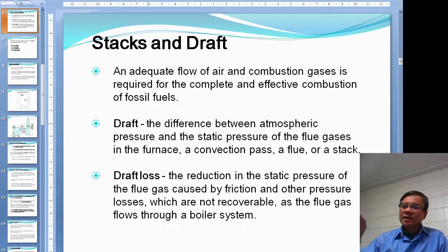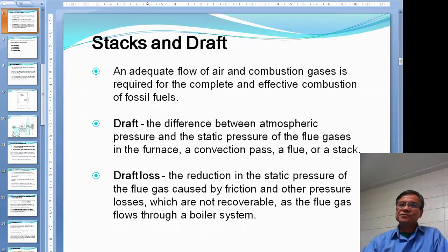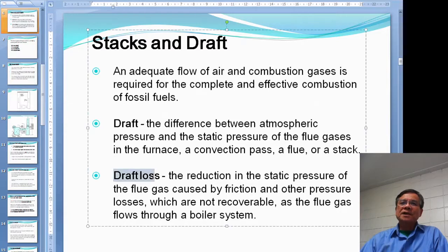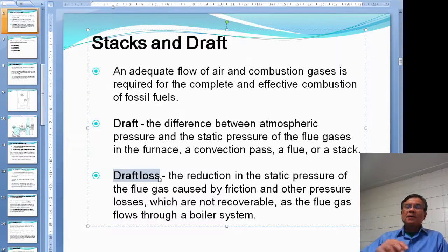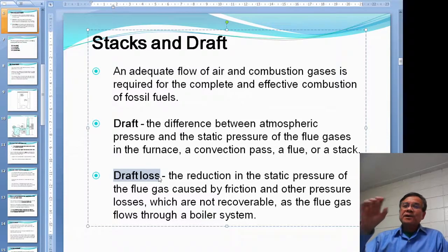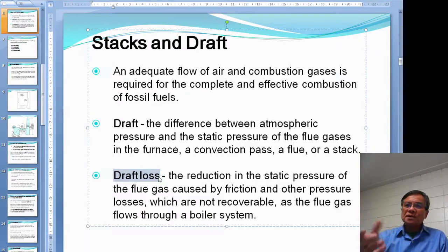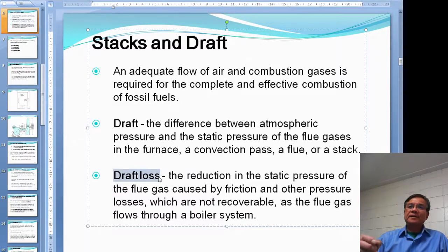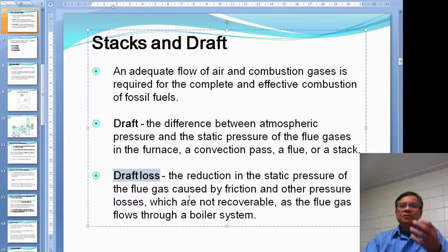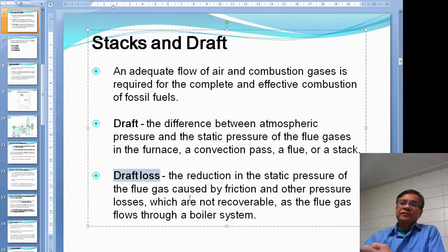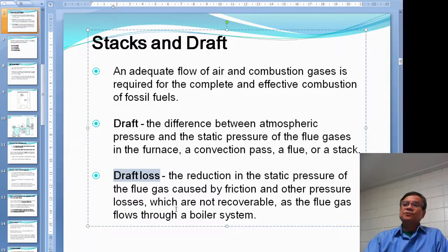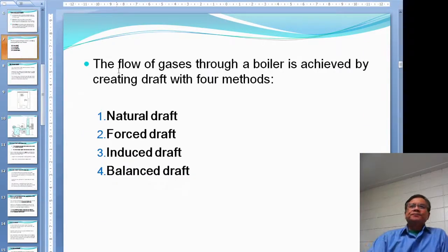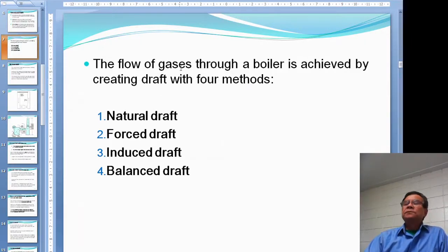There is a difference between the inside and outside atmospheric pressure. Draft loss is defined as anything on the path of the gas that goes through the furnace and then the stack. If you put anything in there, it will reduce the static pressure and cause friction — that is called draft loss. Draft loss cannot be recovered. One example is putting an economizer in the flue gas path, which will create some draft loss.